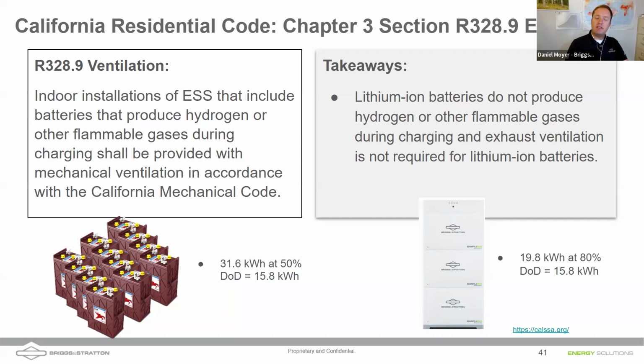Down at the bottom, Nathan, I always thought this was interesting. On the left we've got a bunch of L16 batteries—that's how many you'd need at 50% depth of discharge to get about 16 kilowatt hours usable. On the right, one of our 6.6 stacking batteries at 80% depth of discharge, which can go a little lower on lithiums, gives the same amount of energy storage capacity. We're packing a lot of energy into these batteries, and the discharge rate is a lot quicker on our lithium as well.